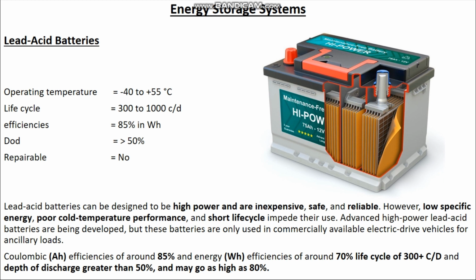You get charge and discharge efficiency of maximum around 85%. And depth of discharge, you just have greater than 50% depth of discharge, maybe you can go 60 to 70% depth of discharge. So you cannot discharge this type of battery to full extent, 100% discharge. If you do, you are going to actually destroy the battery.